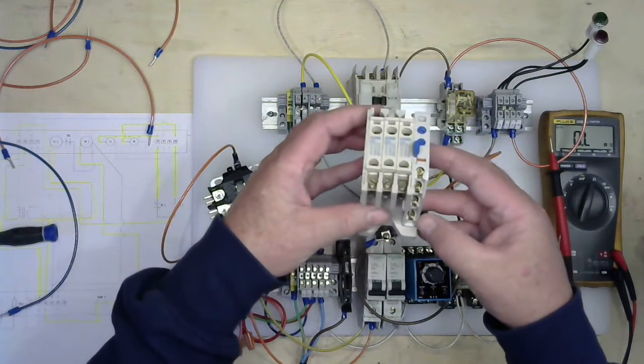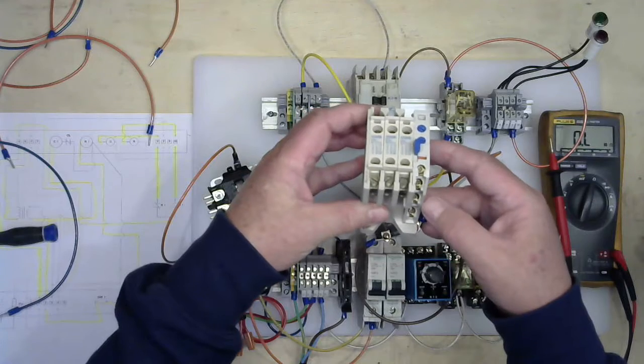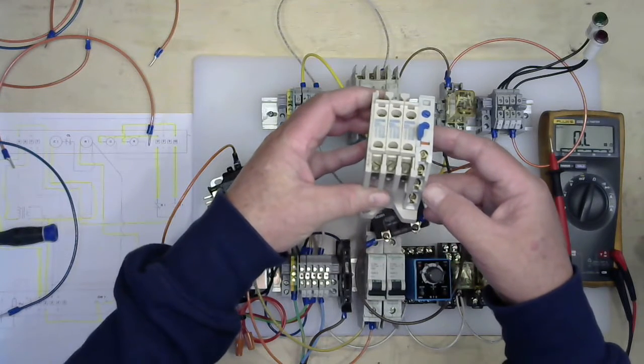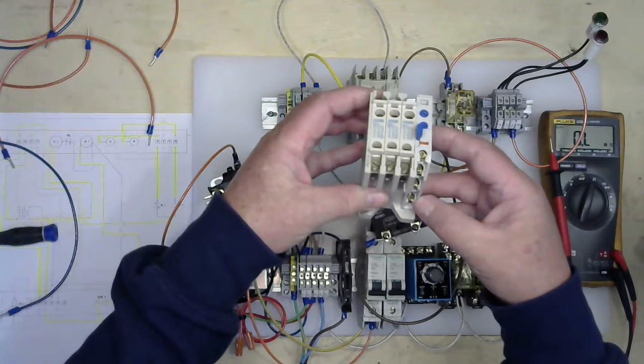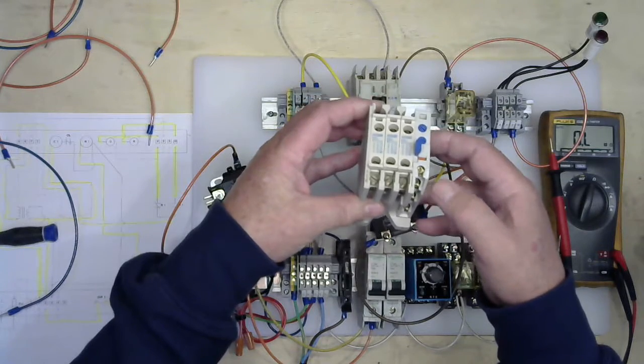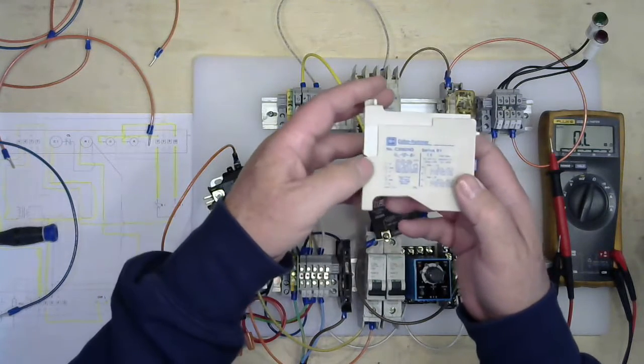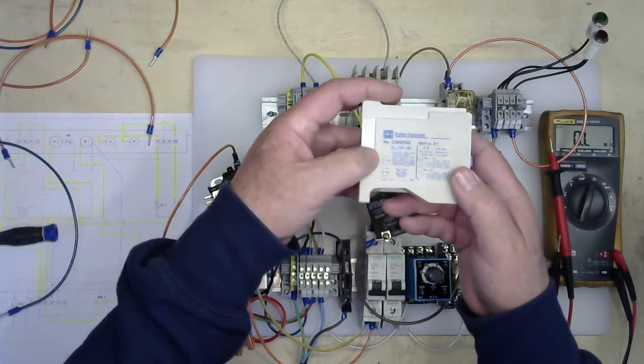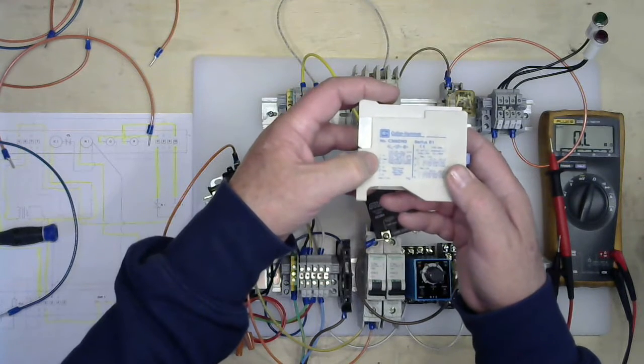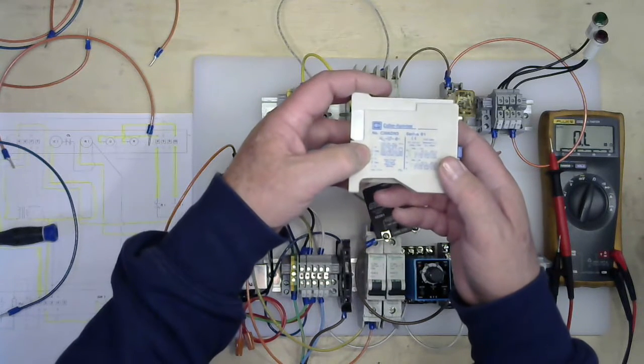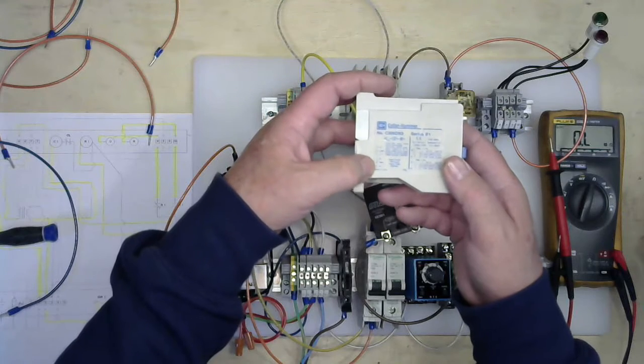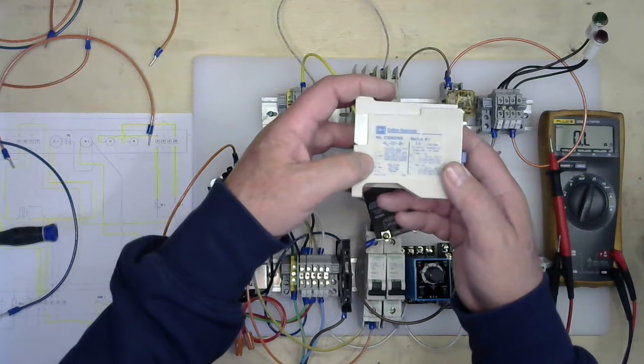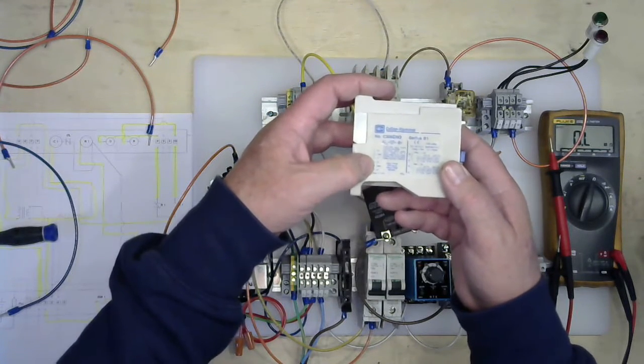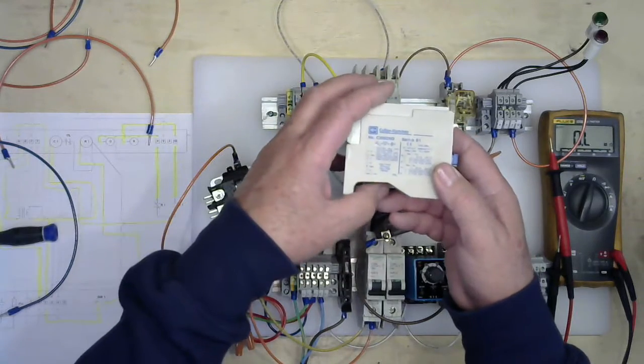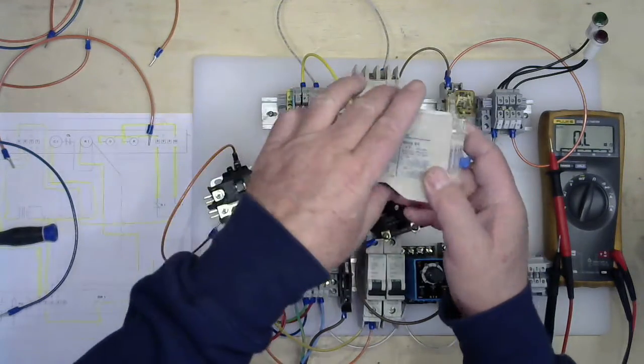If I look at this on the bottom here, it says 95 and 96. Those are the two terminals I did not get continuity on. I did get them on 97 and 98. If I look on the side here again, 97 and 98 are supposed to be open, not closed. Again, that's normally open. 95, 96 are supposed to be normally closed. They were shown open, so I'm showing opposite of what I have. Do I have a bad overload?